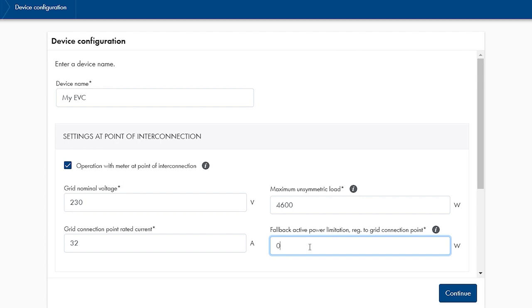Make sure to set a safe value here, which will not overload the house's main fuses. Leaving it at zero will mean the EV charger cannot charge the vehicle in case of a communication disruption to the Sunny Home Manager.